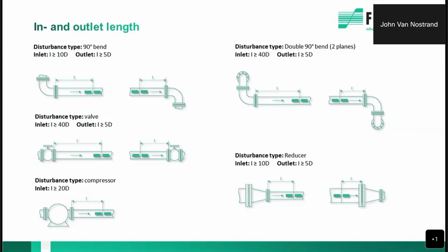So the question often comes up about straight runs. How many straight runs are necessary? Well, the recommendation for direct mount transducers on opposite sides of the pipe is 5 diameters downstream and 10 diameters upstream of an elbow. So many piping systems don't allow for 15 diameters of straight run. So FLEXIM has performed some independent testing, which shows reflect mounting gives an average.